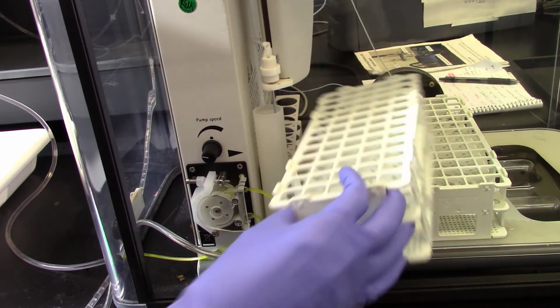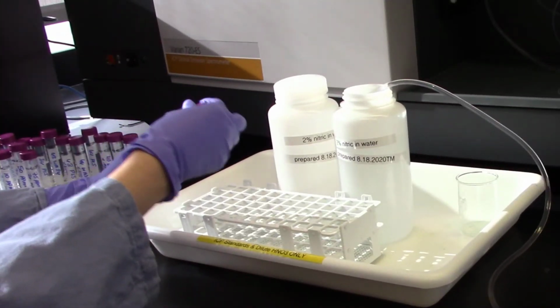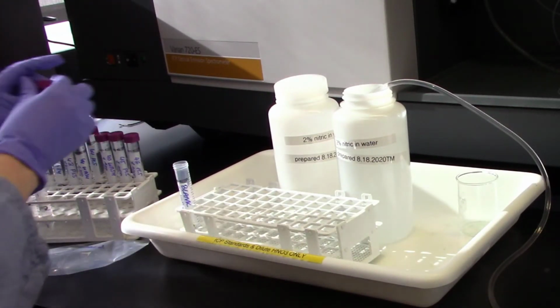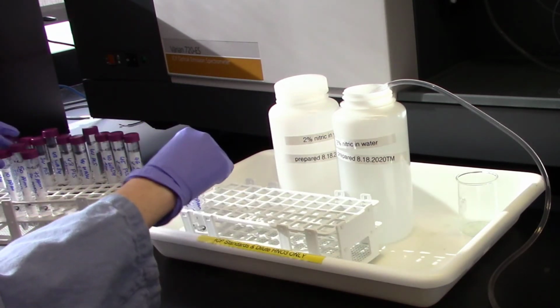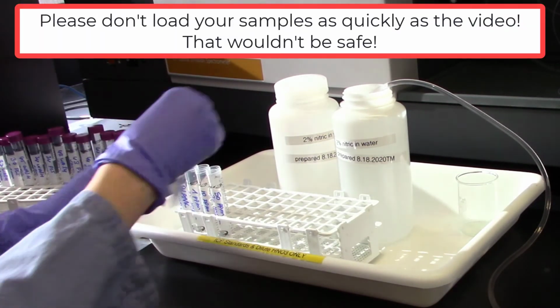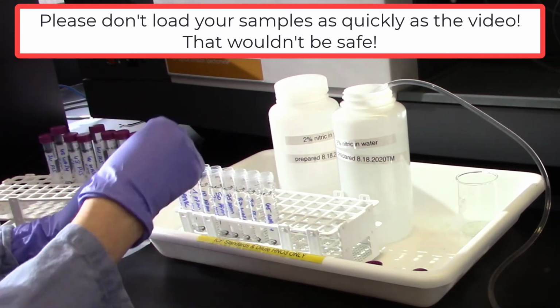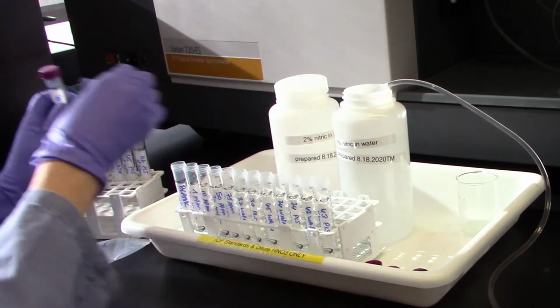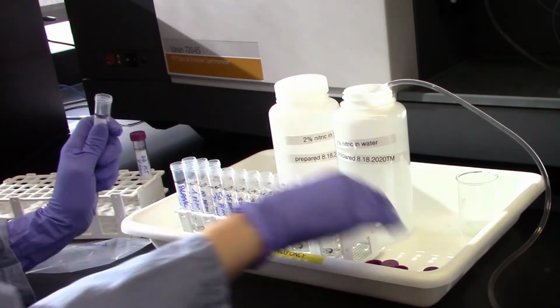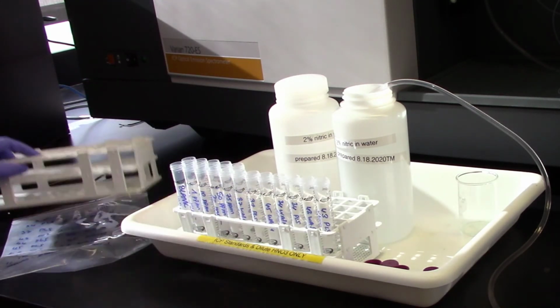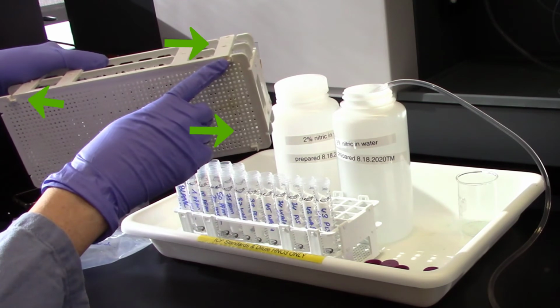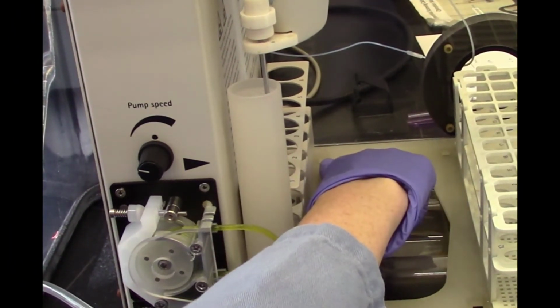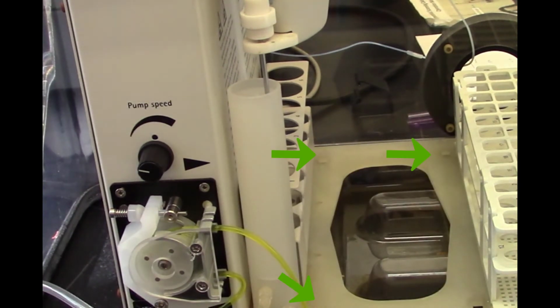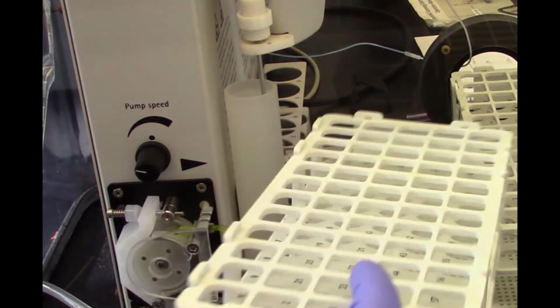The tray can be removed for ease of loading. Remove the caps from your sample tubes and insert your samples starting with the blank. Be sure to use a secondary tray for spills, and never lift these acid solutions over your lap. Acid of any concentration is not friendly to clothing or to skin. You'll notice there are 4 L-shaped feet on the bottoms of the sample trays. These little feet must slide into the open squares at the base of the auto sampler that you can see here. Load your sample tray so that the first position with the blank is in the back left corner.